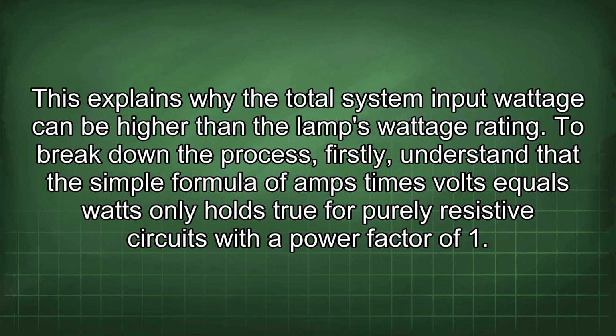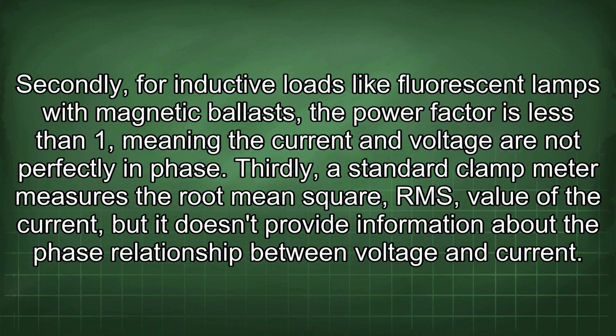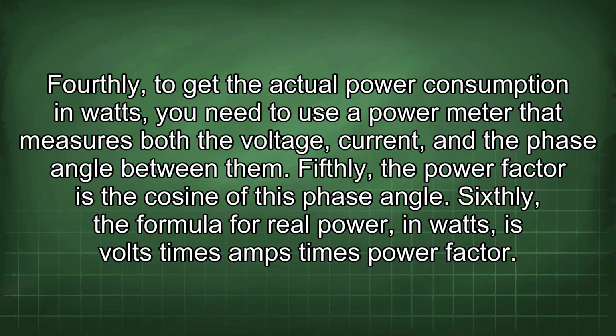To break down the process, firstly, understand that the simple formula of amps times volts equals watts only holds true for purely resistive circuits with a power factor of 1. Secondly, for inductive loads like fluorescent lamps with magnetic ballasts, the power factor is less than 1, meaning the current and voltage are not perfectly in phase. Thirdly, a standard clamp meter measures the root mean square, RMS, value of the current, but it doesn't provide information about the phase relationship between voltage and current. Fourthly, to get the actual power consumption in watts, you need to use a power meter that measures both the voltage, current, and the phase angle between them.